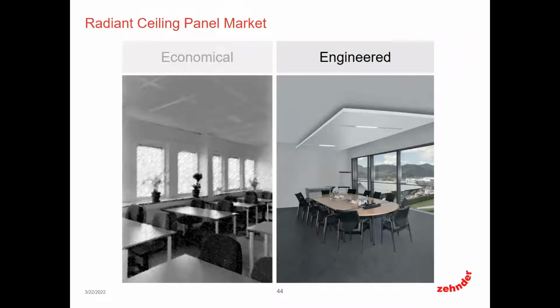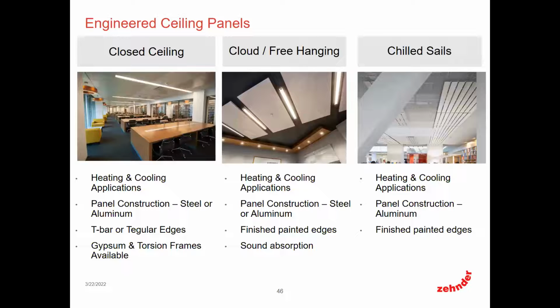If you were to come to us and say, we want to start talking about a radiant cooling application, that's when we're going to start looking at some of the, I'll say, applied product or engineered products. And this is where we start separating from that linear modular market. And this is really where we open up the doors to different installation types, different aesthetics, and we start having a conversation about sound. So whether you're going into a closed ceiling, meaning if this is going into like a lay-in grid or a tegular edge or gypsum hard lid ceiling, those options fall into that category because it's a closed ceiling, basically wall to wall, no free space around the panels themselves. You're not allowing for additional convection.